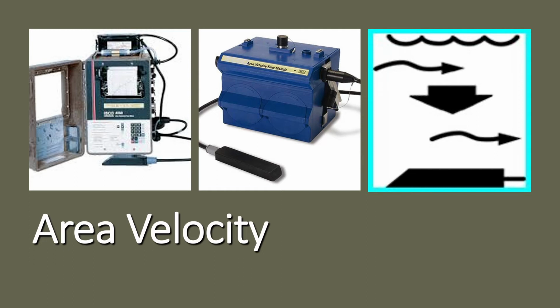Area velocity does have its limitations, and limitations include you must have a level of water flow that's above the height of the area velocity sensor, and you do compromise a little bit of accuracy, because most of the time this is used in a non-primary device application, that being just a partially full pipe.